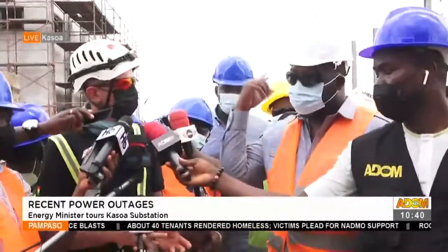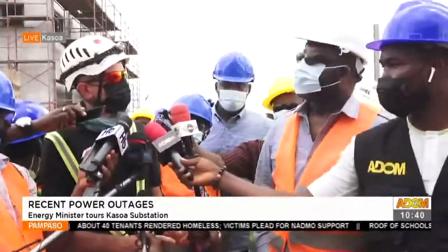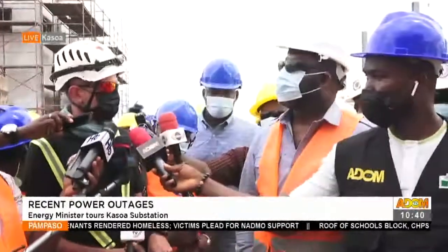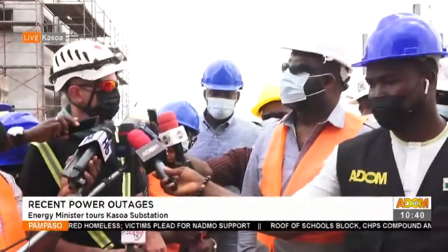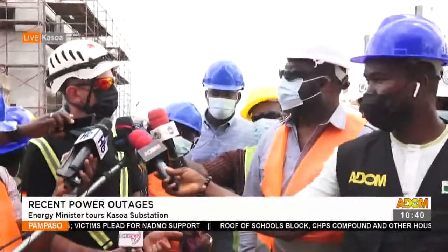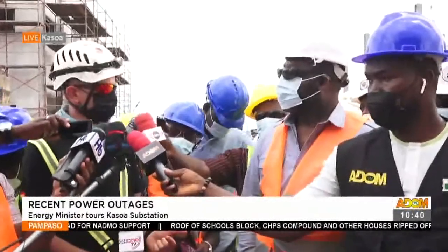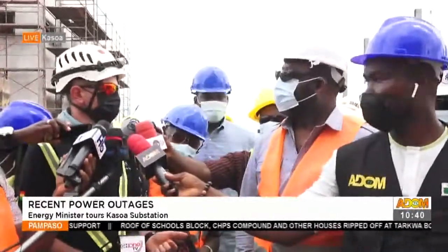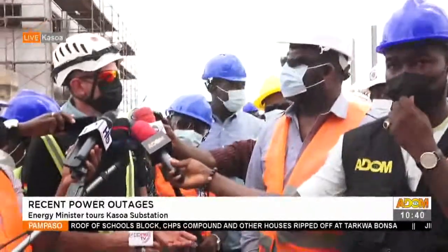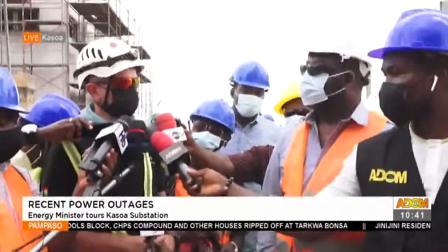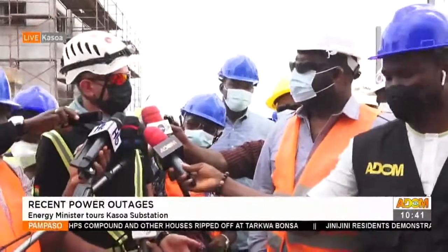We will have an outage, but it's just to allow us to build the new lattice towers. But at the end of this first outage, we will bring the line back from an electrical point of view. It means we will not connect the substation because we still have some work to do, like HV cables, you know, commissioning and things like that. But end of August, that's the second outage.